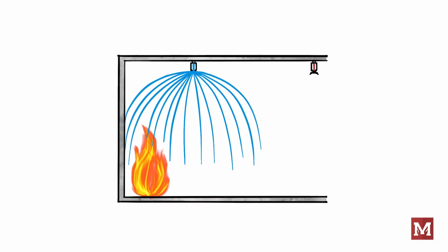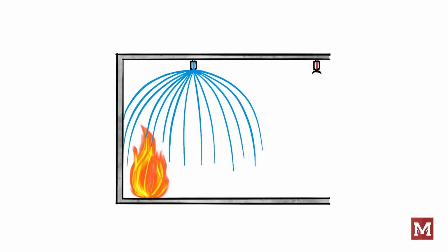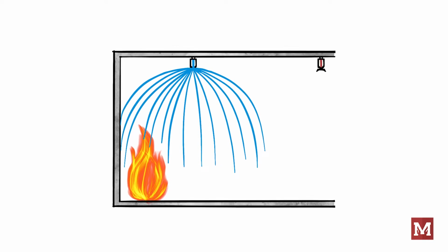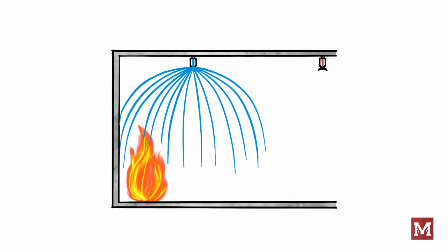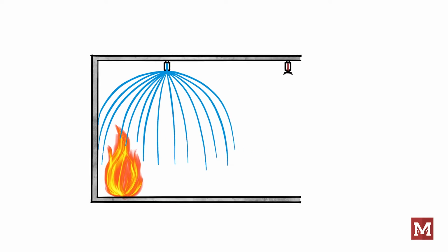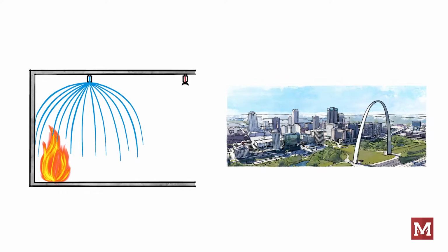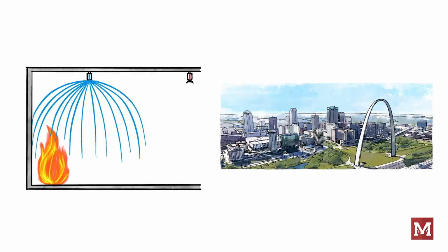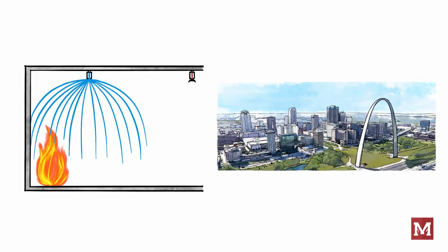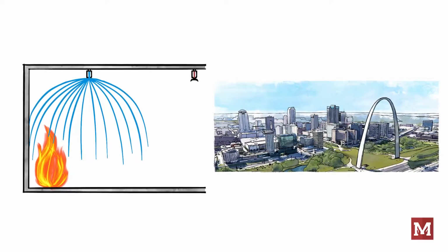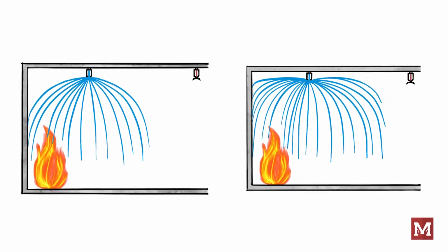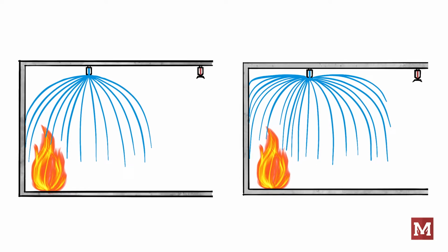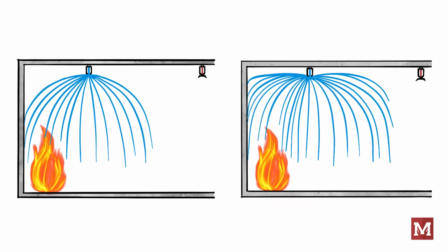The shape of the standard spray sprinkler's pattern is like a parabolic curve spun around on a vertical axis. The intent is to have water distributed relatively evenly across the area it covers. Think of the curve of the St. Louis Arch spun around on a vertical axis, except that water is intentionally thrown in all directions within the curve. Different types of sprinklers, like residential, throw more water towards the outside of the pattern, where residential combustibles are usually found, but the overall spray premise is similar.